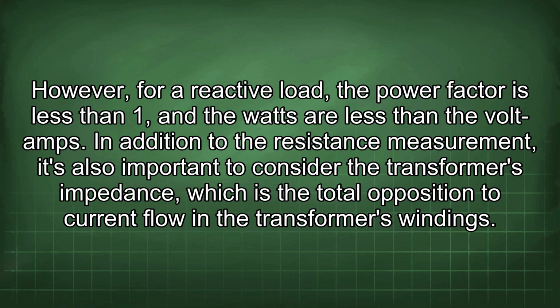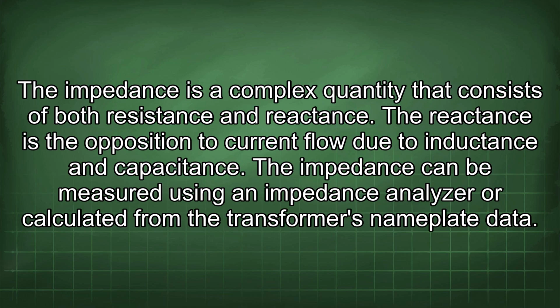In addition to the resistance measurement, it's also important to consider the transformer's impedance, which is the total opposition to current flow in the transformer's windings. The impedance is a complex quantity that consists of both resistance and reactance. The reactance is the opposition to current flow due to inductance and capacitance. The impedance can be measured using an impedance analyzer or calculated from the transformer's nameplate data.